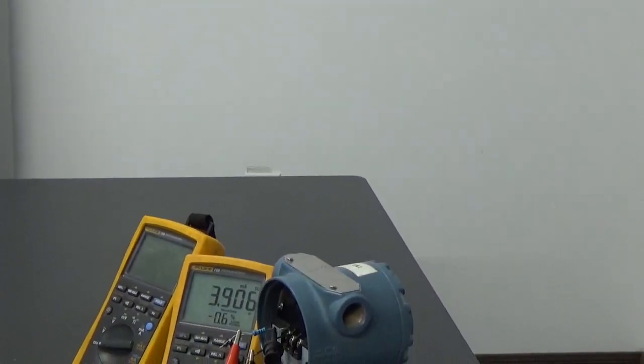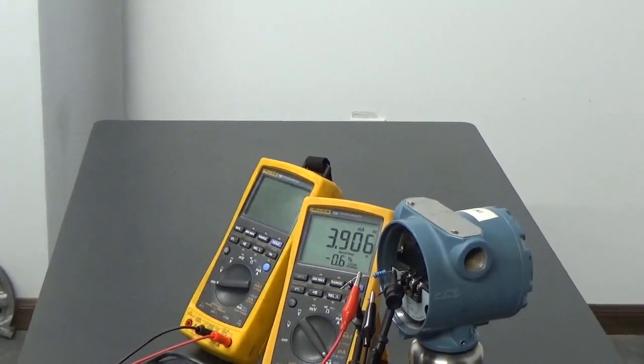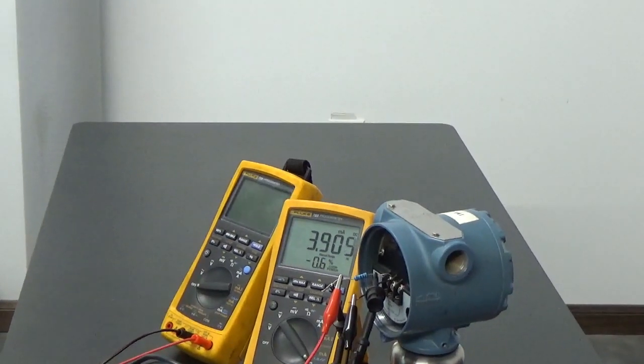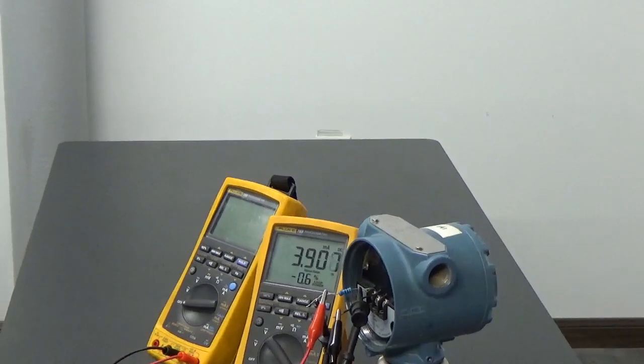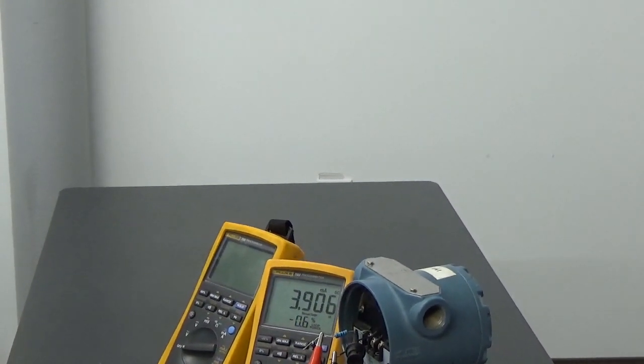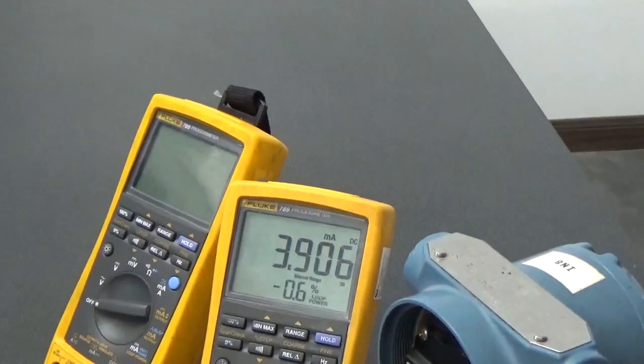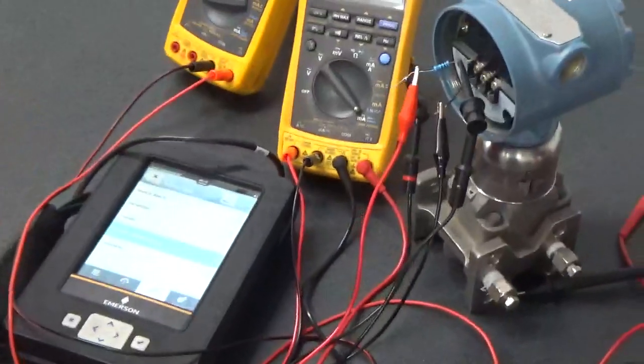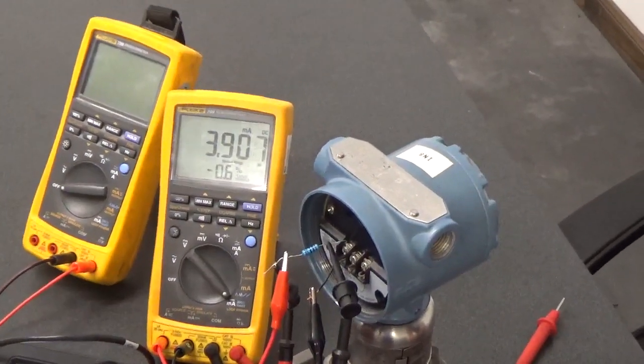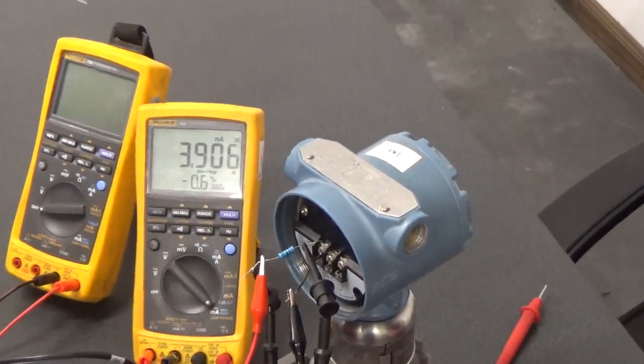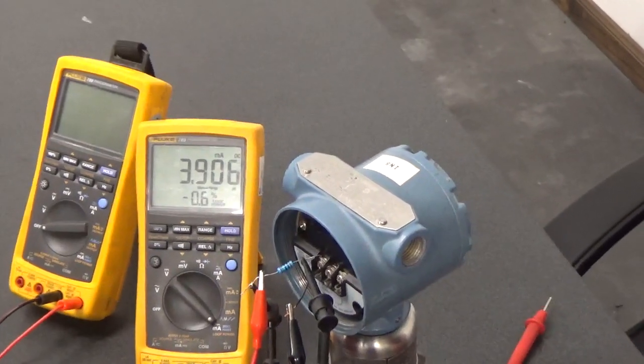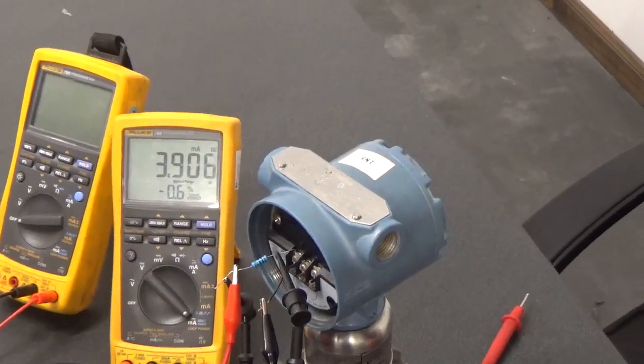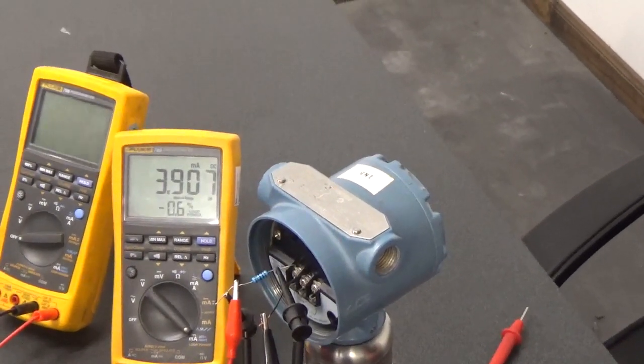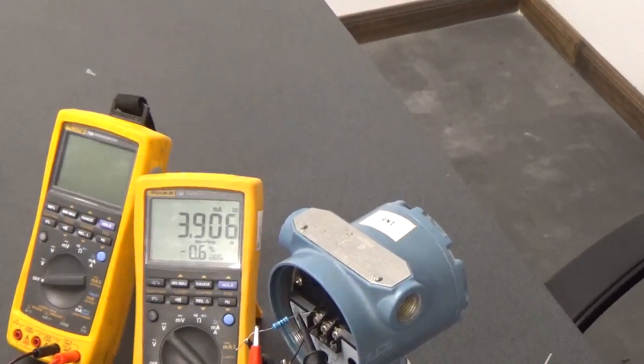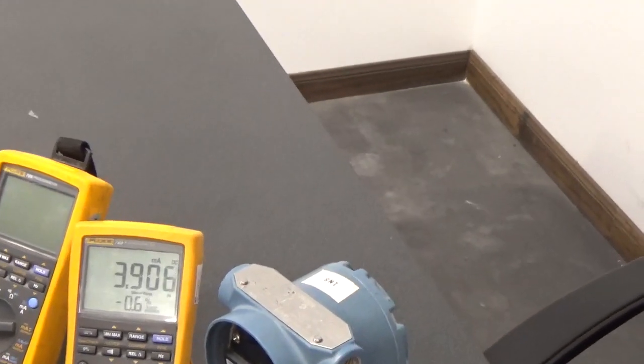We're gonna do something a little bit different, Raul. Go ahead and go into service tools. Go into calibrate. Let me see. Routine maintenance. Let's look at routine maintenance. You see where it says analog output calibration? Yes. See, this is a pressure transmitter, but you can also do analog output calibration right there. Now, this is how you calibrate your analog signal. Digital to analog trim right there, okay. That's just a normal warning. Connect reference meter, it's already connected. We got a reference meter, okay. Setting field device output to 4 milliamp, push okay.